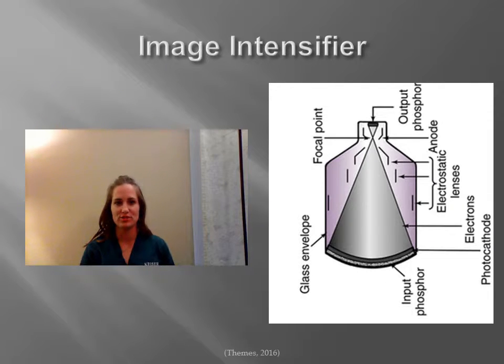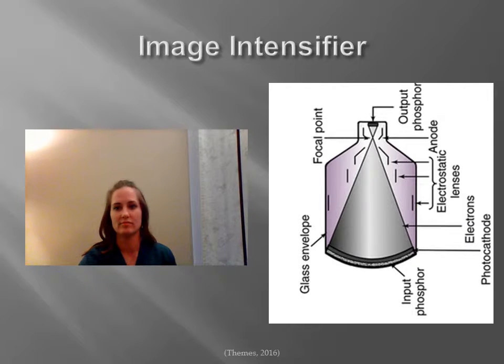The image intensifier tube is used to increase illumination of the image and to make a wide range of contrast more visible. KVP, MAS, and patient thickness influence how much illumination may be produced. The image intensifier essentially increases the amount of output photons performed in a series of steps to increase image brightness. Magnification also occurs in the image intensifier. For example, increasing magnification will produce a smaller field of view, but increase patient dose and reduce brightness.